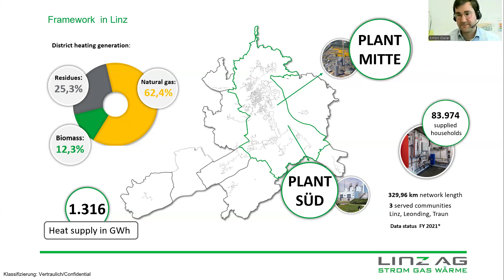Let's see how we currently handle our heat peak loads. For example, on a cold winter day at minus 10 degrees, we need a power generation of 500 megawatts. To supply this 500 megawatts thermal power for our district heating network, we use different plants. The first two are the gas CHPs, with extraction condensing and back pressure turbines at both Mitte and Süd. If we bypass the steam turbine, we get a slightly higher thermal power, as you can see.